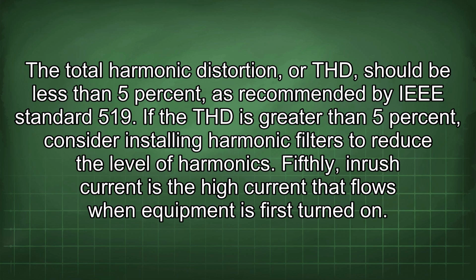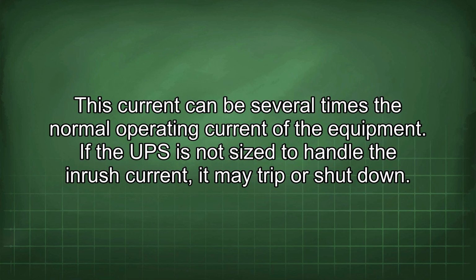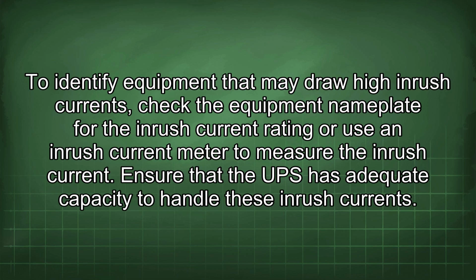Fifthly, inrush current is the high current that flows when equipment is first turned on. This current can be several times the normal operating current of the equipment. If the UPS is not sized to handle the inrush current, it may trip or shut down. To identify equipment that may draw high inrush currents, check the equipment nameplate for the inrush current rating or use an inrush current meter to measure the inrush current. Ensure that the UPS has adequate capacity to handle these inrush currents.